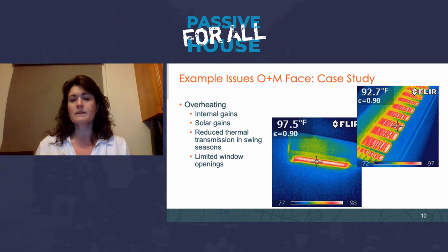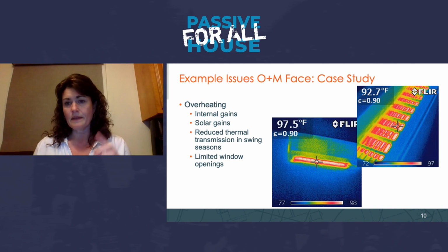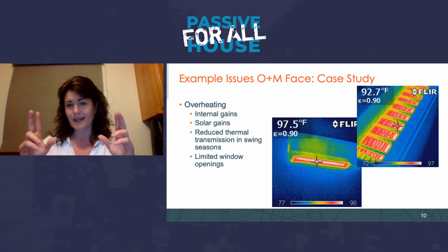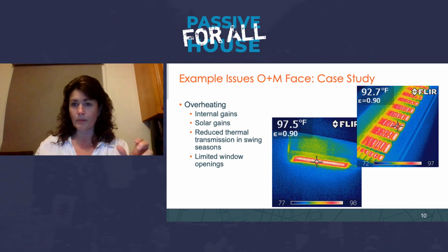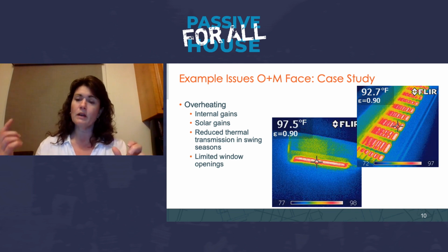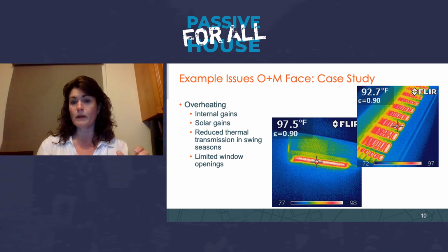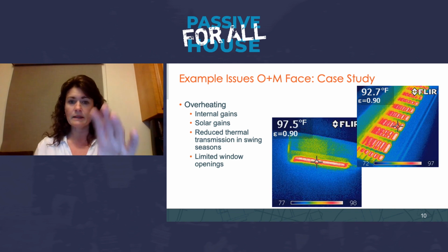One of the things, and this is happening in most of our multifamily affordable units that do not have heat recovery, because the system is either in heating or cooling, is there's just really one loop. Most of the units on one loop, indoor units, are considered kind of charged. If one person on that loop is calling for heat, refrigerant flows at a certain minimum rate through the whole loop.